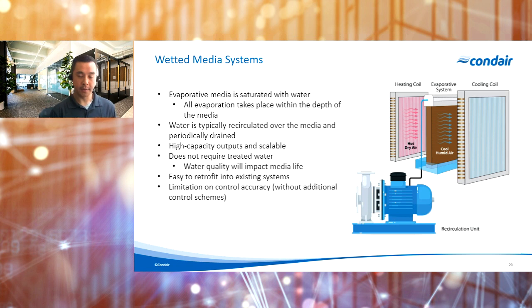So with this type of system, as I mentioned, very little energy is really required to operate it. Really, it's just the power needed to pump water over the top of the media. There will be some additional fan power required to overcome the pressure drop across that media, but really in comparison to a traditional isothermal humidification system or even a DX cooling system, the amount of energy that we're using here is significantly less.